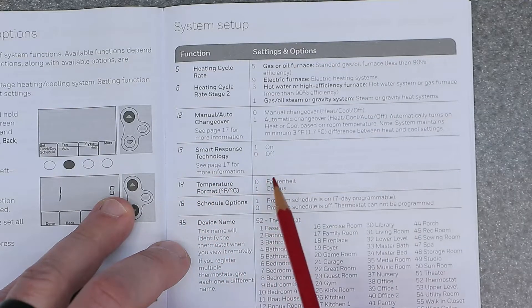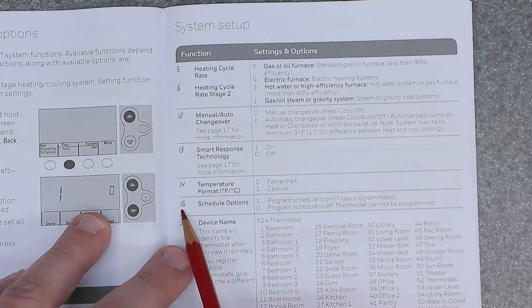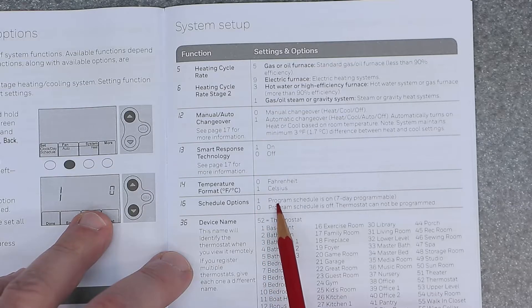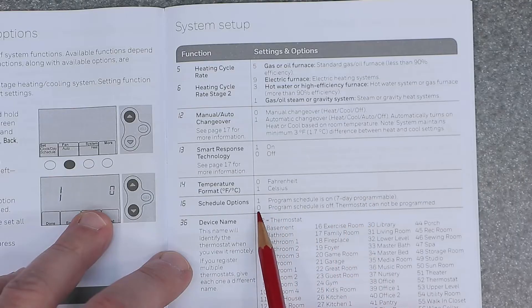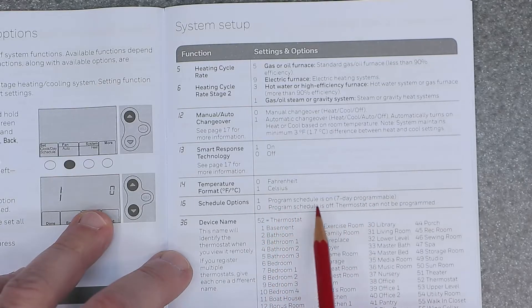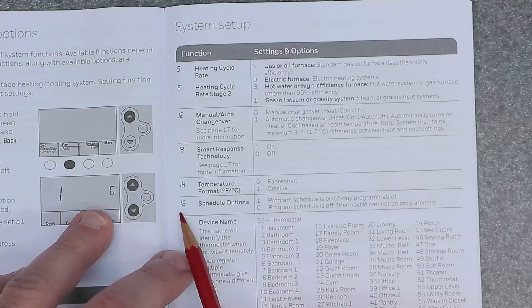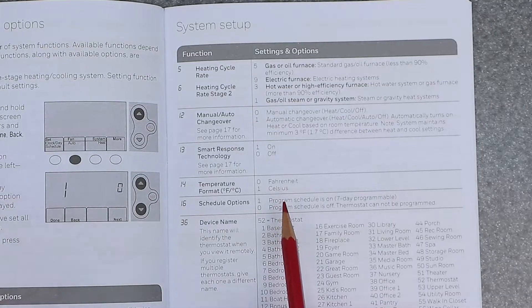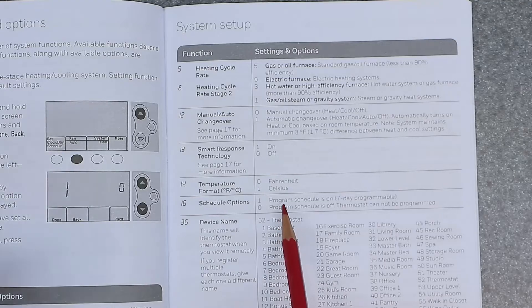Number 14 is temperature format. So zero is Fahrenheit. One is Celsius. 16 is schedule options. One is program schedule is on, seven day programmable. And zero is program schedule is off. Thermostat cannot be programmed. So this here, number 16 is if you want to operate it as a complete manual thermostat, non-programmable. You can go ahead and do that and make it the most basic thing ever.